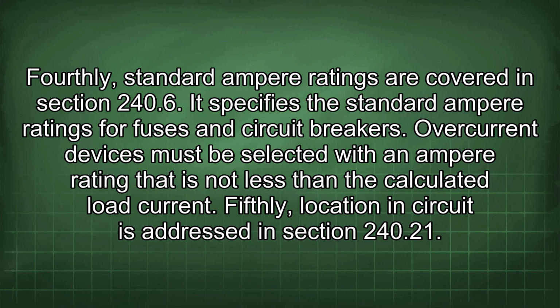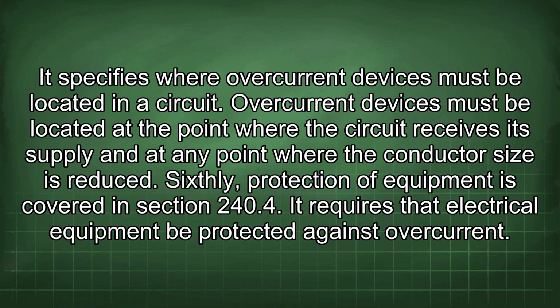Fifthly, location in circuit is addressed in Section 240.21. It specifies where overcurrent devices must be located in a circuit. Overcurrent devices must be located at the point where the circuit receives its supply and at any point where the conductor size is reduced. Sixthly, protection of equipment is covered in Section 240.4. It requires that electrical equipment be protected against overcurrent.